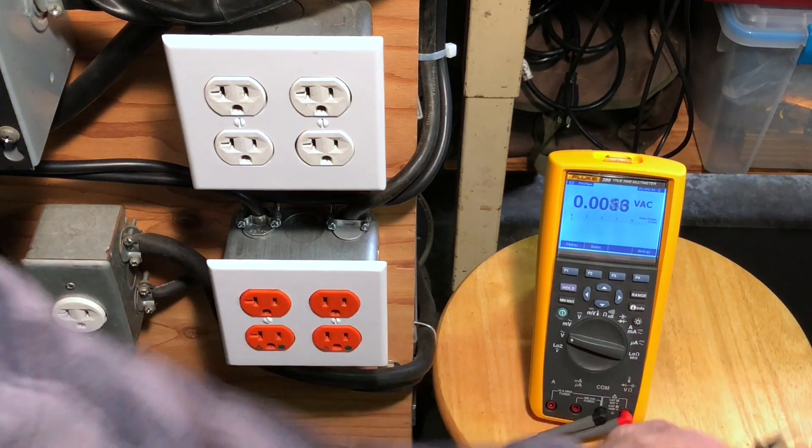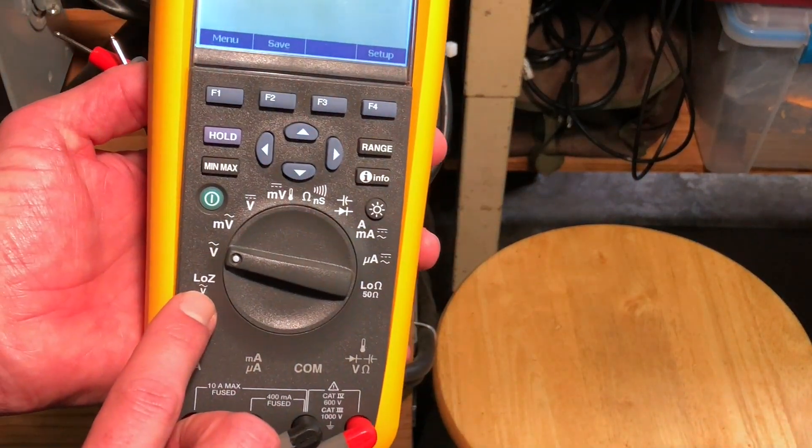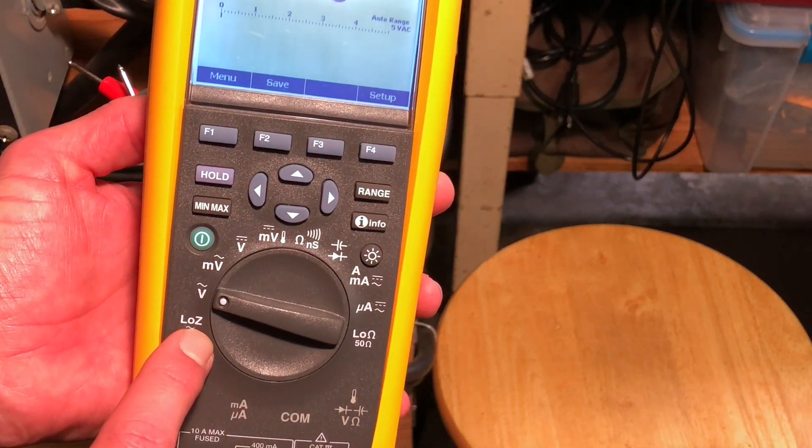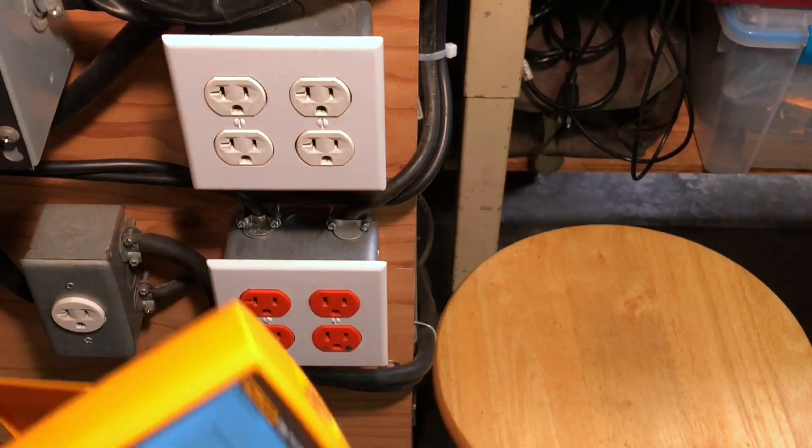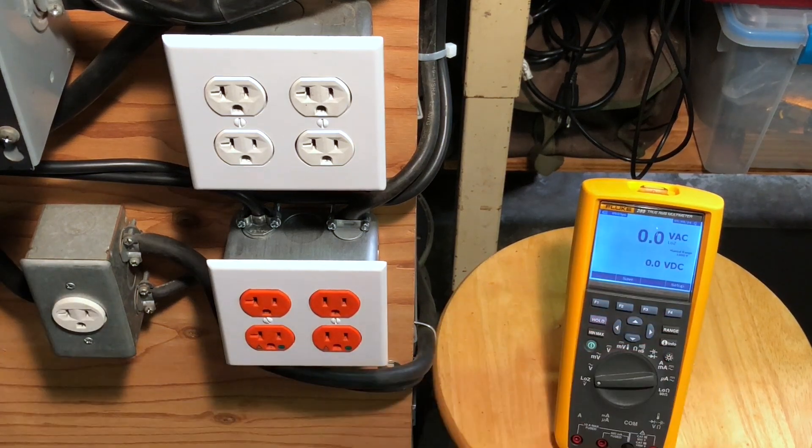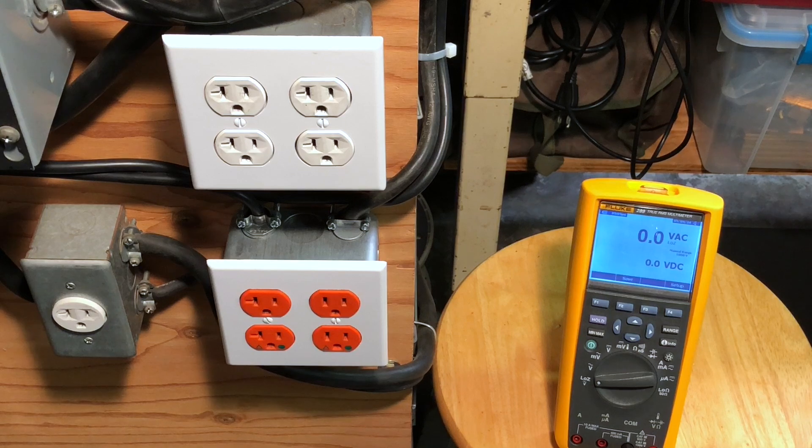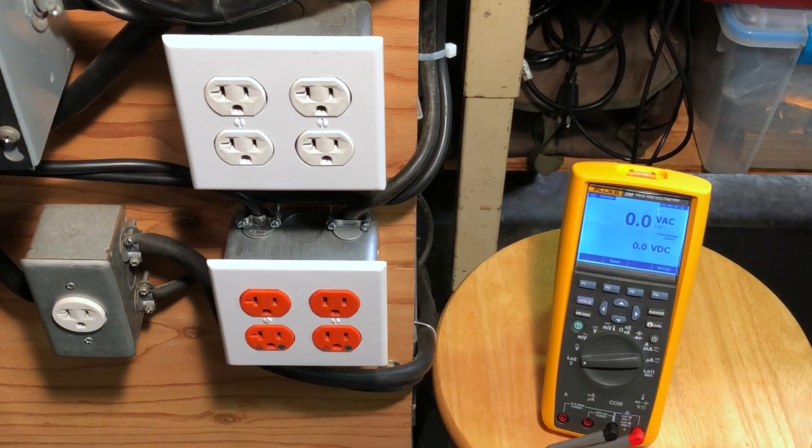Let's look at what a low impedance is. If I grab my Fluke 289 and show you on the front panel, see it says low Z right there. Z is the symbol for impedance, and that is the low impedance mode. It takes the impedance of this digital multimeter that was up in the 10 mega ohm range or possibly higher than that and drops it way down into just the thousands of ohms. Conveniently, it measures volts AC and volts DC at the same time, a very nice feature.